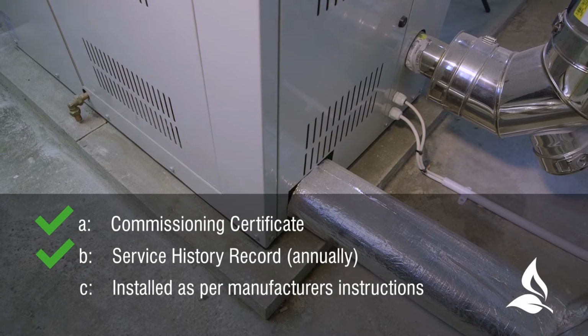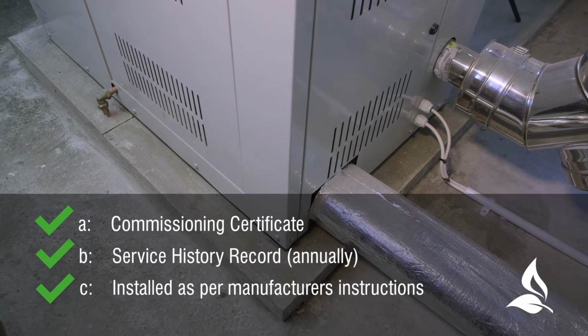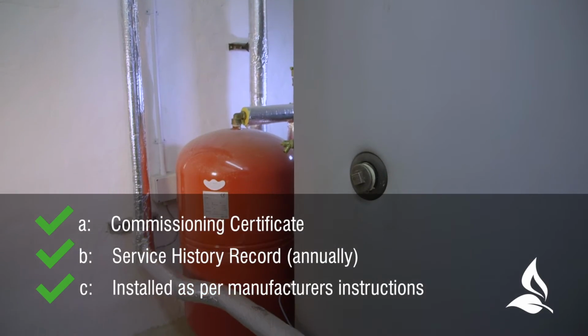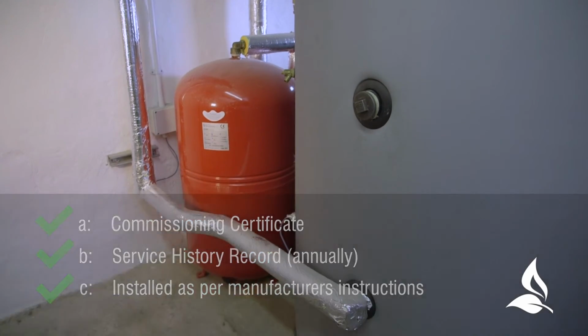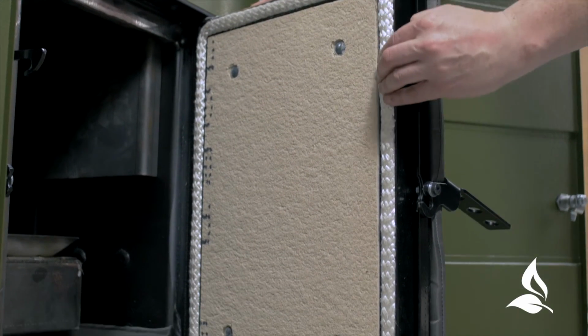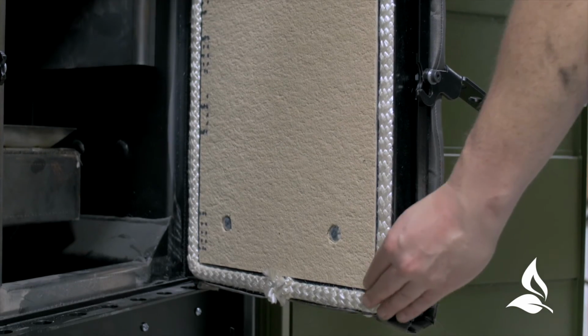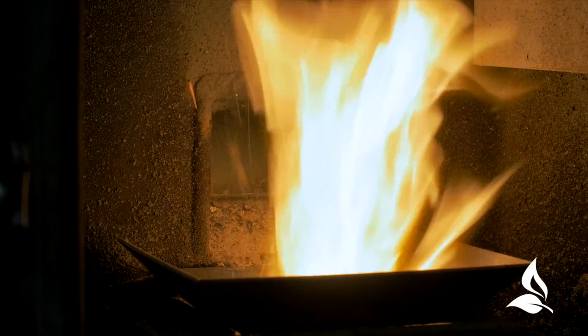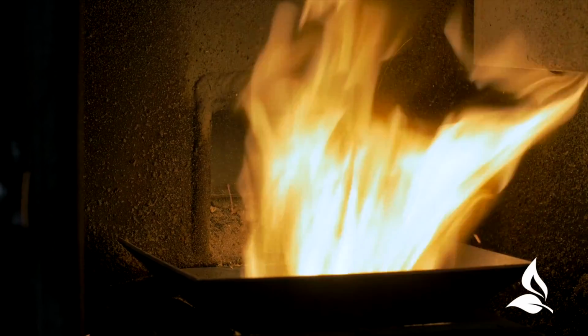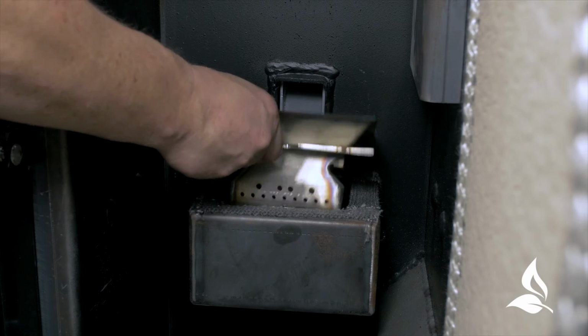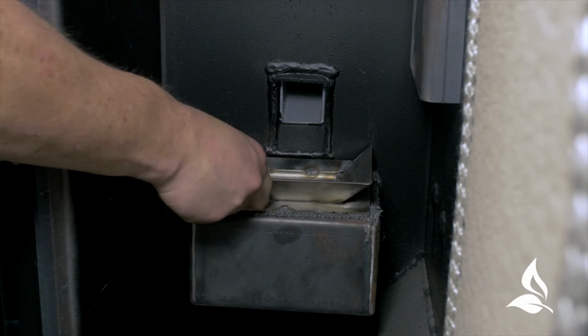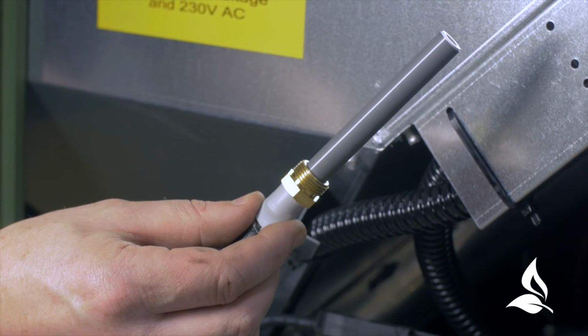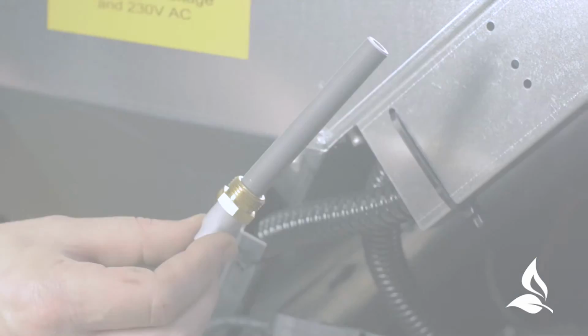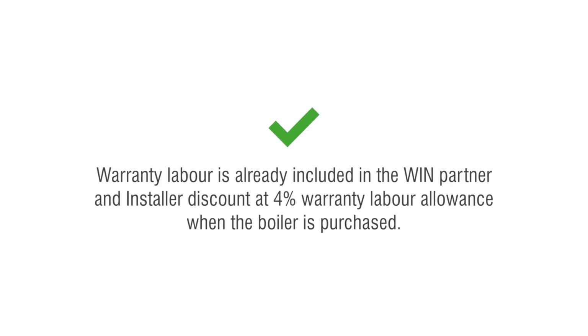C. Boiler must be installed in accordance with manufacturer's instructions. An area where installers often fall down is sizing the expansion vessel correctly. Parts such as rope, fiberboard, and parts in direct contact with the flame, such as grate, ashpan, etc., are considered consumables and not warrantable. These items may need replacing during a service. There is a 1-year warranty on the ceramic igniter. Warranty labour is already included in the Partner and Installer discount at 4% warranty labour allowance when the boiler is purchased.